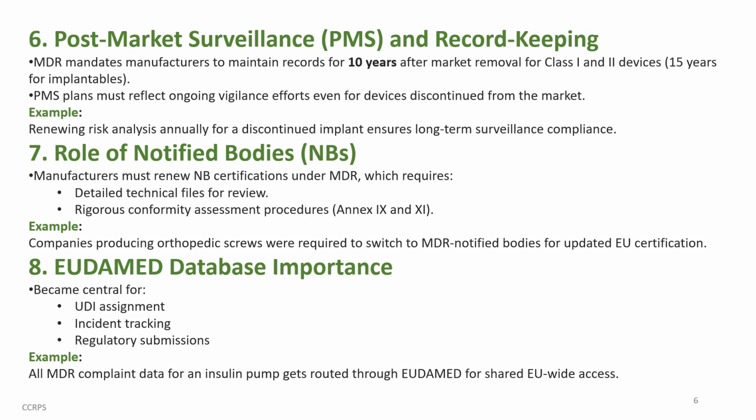Post-market surveillance and record keeping. MDR mandates manufacturers to maintain records for 10 years after market removal for Class 1 and 2 devices, or 15 years for implantables. PMS plans must reflect ongoing vigilance efforts even for devices discontinued from the market. For example, renewing risk analysis annually for a discontinued implant ensures long-term surveillance compliance.